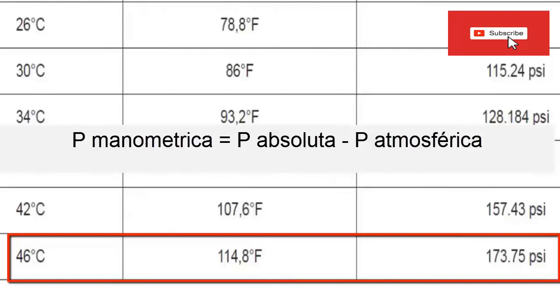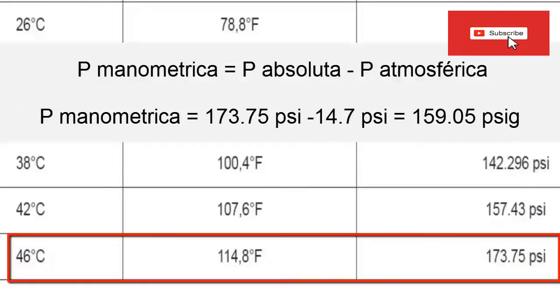Since the table value refers to absolute values, we must subtract the atmospheric pressure of the place where the equipment is located, which for this case we take as 14.7 PSI. By subtracting 173.75 PSI minus 14.7 PSI, a gauge pressure for the condenser of 159.05 psig is obtained.